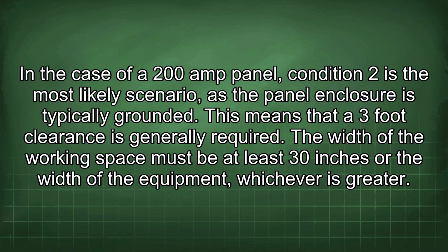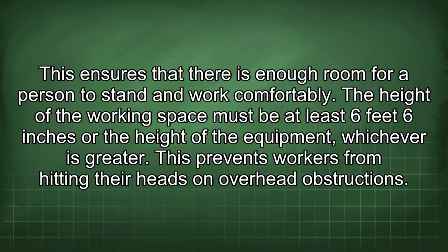The width of the working space must be at least 30 inches or the width of the equipment, whichever is greater. This ensures that there is enough room for a person to stand and work comfortably. The height of the working space must be at least 6 feet 6 inches or the height of the equipment, whichever is greater. This prevents workers from hitting their heads on overhead obstructions.